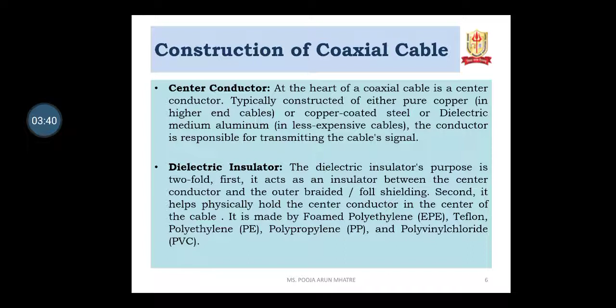Second one is the dielectric insulator. The dielectric insulator's purpose is twofold. First, it acts as an insulator between the center conductor and the outer braided shielding. Second, it helps physically to hold the center conductor in the center of the cable. It is made of foam polyethylene, Teflon, polyethylene, polypropylene and polyvinyl chloride.